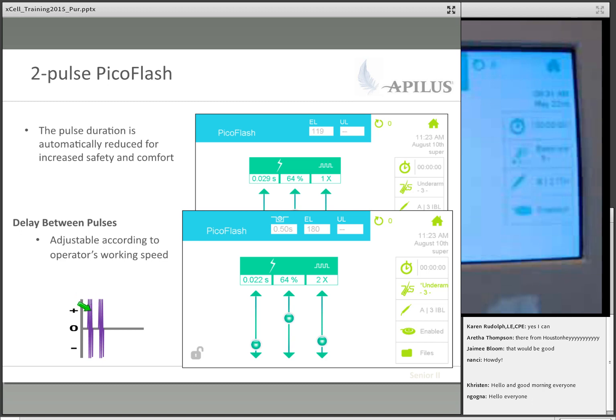And so when you're delivering the second pulse, your tissues are already warmed up a little bit. And so that second pulse could be much more intense. So taking that into account, it just makes all of them a little bit less intense. I believe it's 25% less or something like that. And then when you have the energy level calculation, this is overall energy level, meaning for 2 pulses, it is 180 versus being manual, that would be at 238. So you have less energy being delivered just because you're delivering it in pulses, and it takes into account that your tissues retain some of the heat.